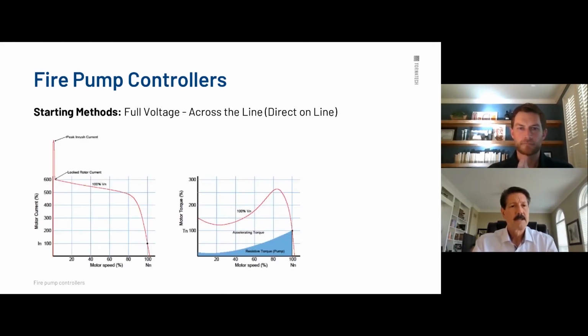Here's the curve. All right, look at the inrush here. We got an inrush right here, roughly 6 times full load amperage. You do have an incremental peak inrush. It's almost negligible. It happens so fast. But as your RPM increases toward full RPM, whether it's 1750 or 3600 or whatever it might be, as you increase your speed, you notice the amperage goes down. And so here's the optimum spot right here. We're at full speed and full load running amperage.